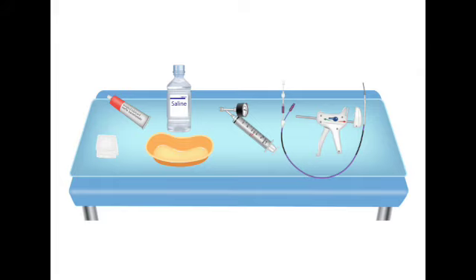And then position 3, neutral. Why is that position so important? Why can't you just leave it in deflation while you're, say, connecting the catheter? That's an excellent question. The neutral position is your safety setting. It locks the whole internal mechanism, so you can make adjustments like sliding the syringe in, securing the clip, screwing on the catheter without accidentally applying any pressure or moving any fluid. It prevents any accidental inflation or deflation while you're still putting the system together. Exactly. It maintains the system's integrity. Okay, so once those handle positions are understood, we get to the most meticulous part of this whole thing, the air and fluid management. Right? And the critical principle here is the complete elimination of air. Precisely.